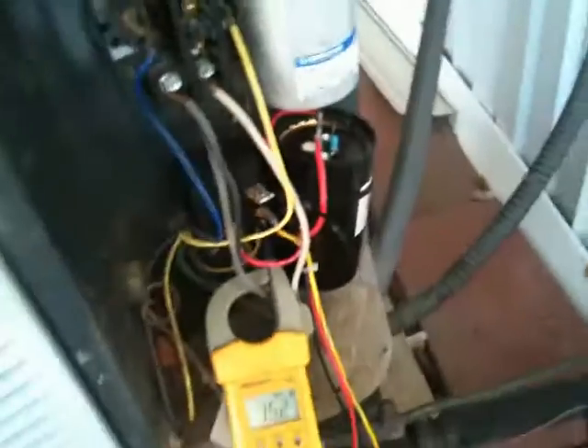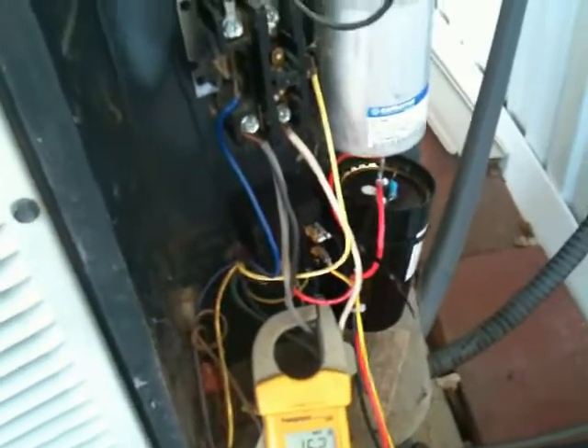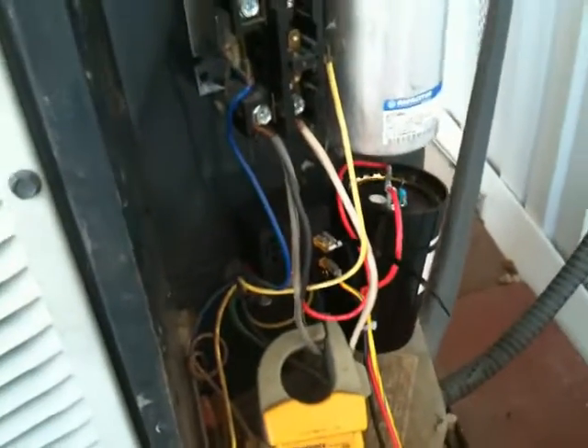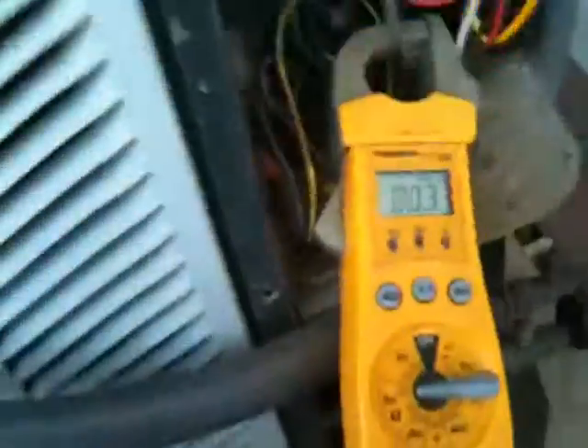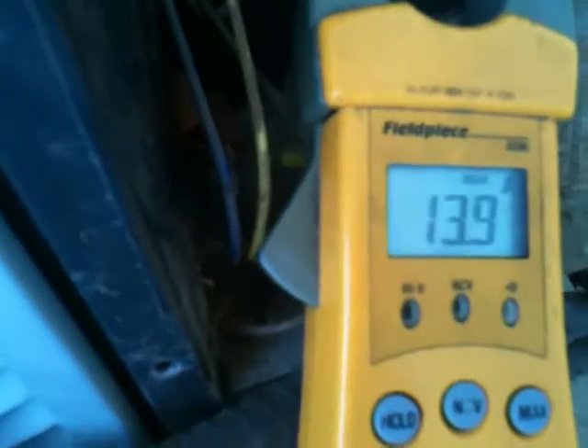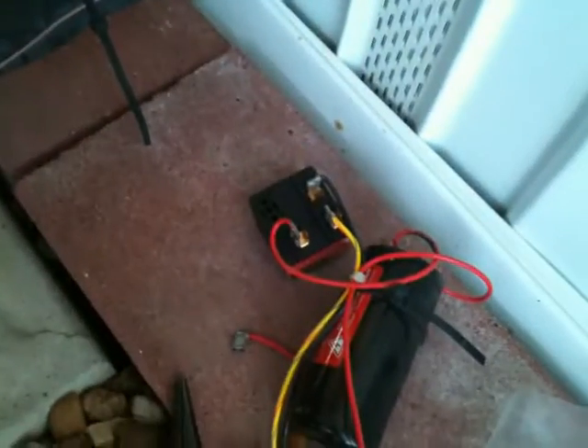I'm going to wire this up and fire it up here. I have the new hard start kit in — see the nice, crisp, clean drop-in resistor on there. I have my meter already set to max and hold. I'll get the screwdriver on the contactor — remember, this is technicians only — and fire it up. We have 13.9 amps, which tells me that even though the bleed resistor was fried, the hard start kit was still functional.